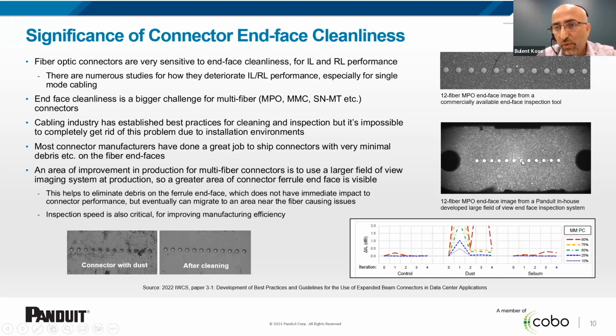On the right-hand side here, the upper right picture shows a pretty good commercially available end-face inspection tool that shows all of the fibers. But at the bottom is a system that we've developed in-house here at Panduit, where we have a much larger field of view. The reason for this would be, in case there is some debris or dust in an area where the imaging system couldn't see, and then this was shipped, that dust or debris can travel to the middle of the connector and contaminate the fibers. So this would be a good way to improve the end-face cleanliness in production.